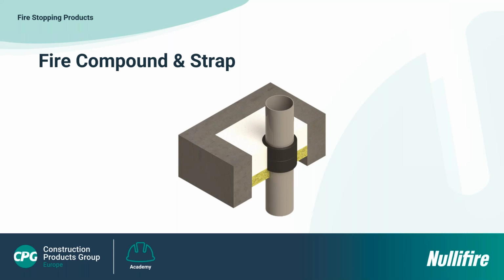And then going back to that previous slide when it's talking about load bearing, if you're wanting load bearing, this tends to be the product you'd go to. And in the case of the combustible pipes, they melt and that strap will fill in with the intumescent material. Compound comes in a powder form. It's just mixed with water, poured into a hole in the floor with a shutter bat used to allow it to set. And then the compound itself holds itself against the substrate, so it gives it its own strength within the substrate. So the shutter bat basically becomes sacrificial and would just burn away. The bat also controls the amount to make sure that you've got your 100 mil pour in there as well.